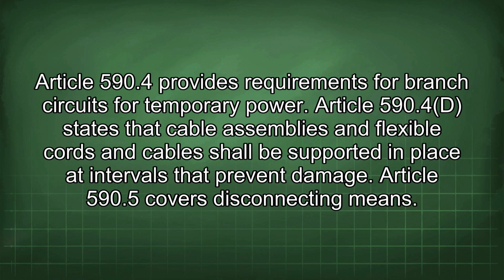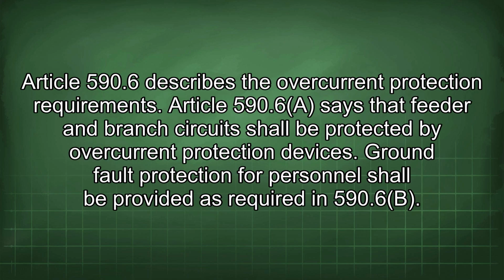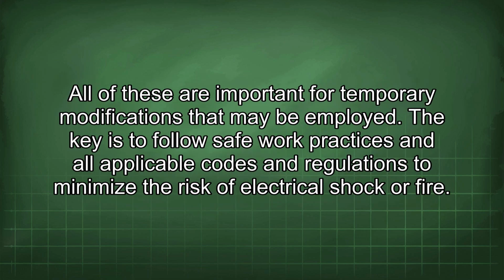Article 590.5 covers disconnecting means. Article 590.6 describes the overcurrent protection requirements. Article 590.6 says that feeder and branch circuits shall be protected by overcurrent protection devices. Ground fault protection for personnel shall be provided as required in 590.6(B). All of these are important for temporary modifications that may be employed. The key is to follow safe work practices and all applicable codes and regulations to minimize the risk of electrical shock or fire.